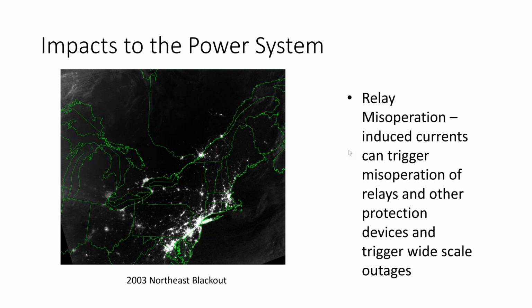I've got a picture here, obviously, from the 2003 blackout that occurred in the Northeast. If we got into a situation where a significant number of the relays misoperated, you could certainly trigger what's called a cascading outage that would take out significant portions of the system. And that's exactly what occurred in the 2003 blackout, when the electrical outage rippled up from northern Ohio through Pennsylvania and New York into Canada and down through Michigan and caused that northeast blackout. So relay misoperation is another particular concern that has to do with the digital relays.